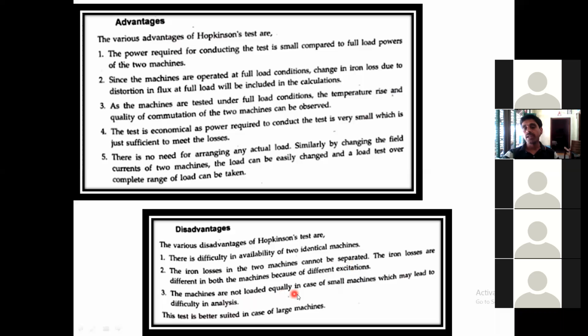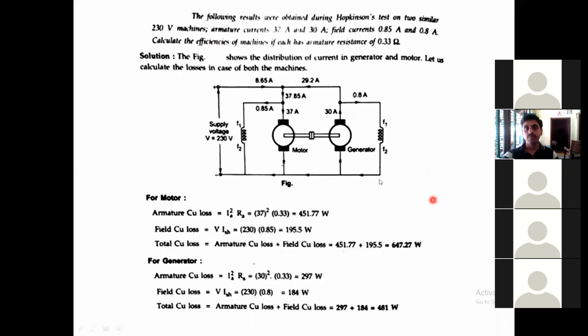The machines are not loaded equally in the case of small machines, because we said that this test is more suitable for large machines. For small machines, there are some issues. But anyway, with regenerative feedback it gives an efficiency almost equal to the actual efficiency, though these are all indirect tests. If you take one problem, I have discussed this very clearly line by line in the video lecture. You go through that line by line.